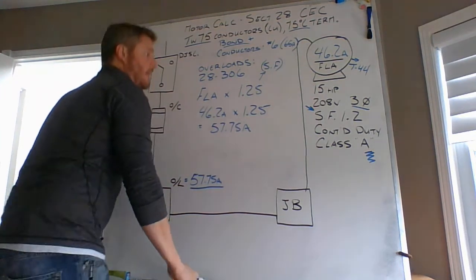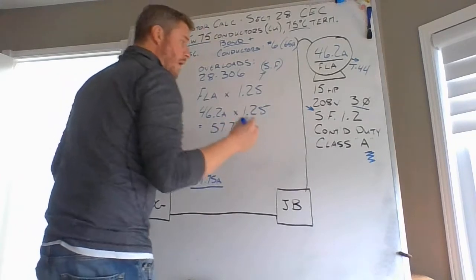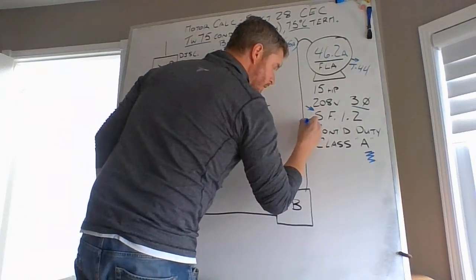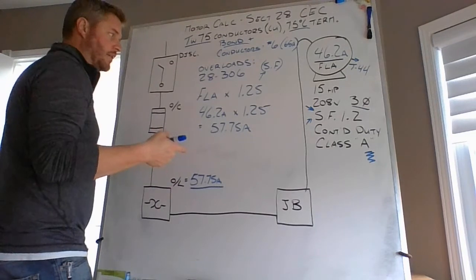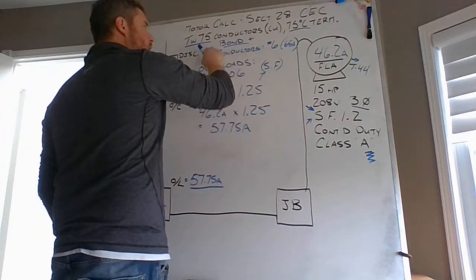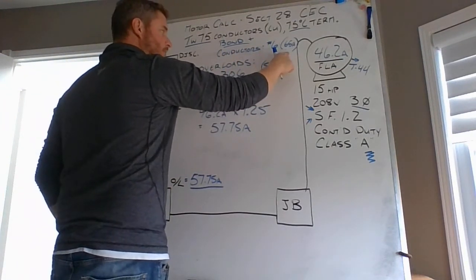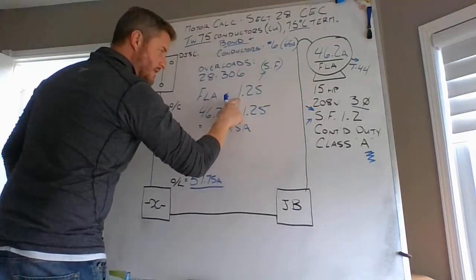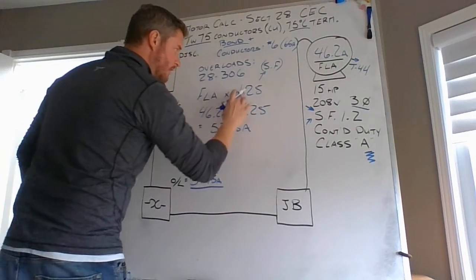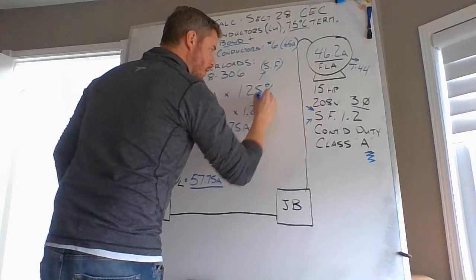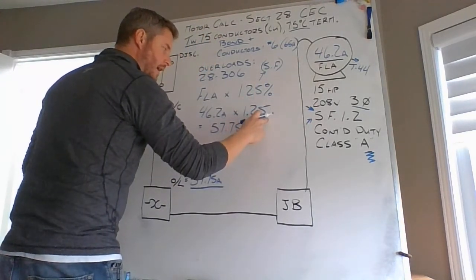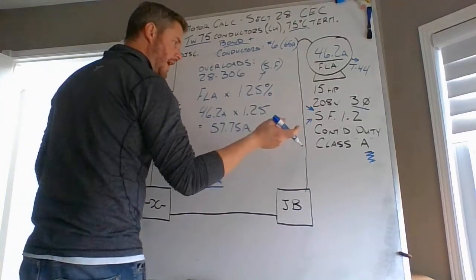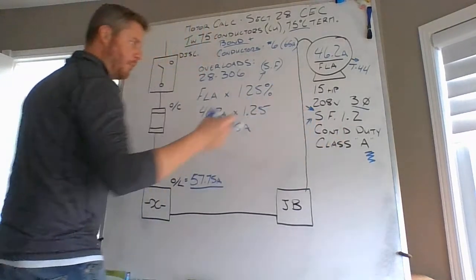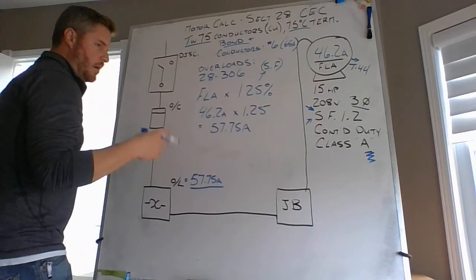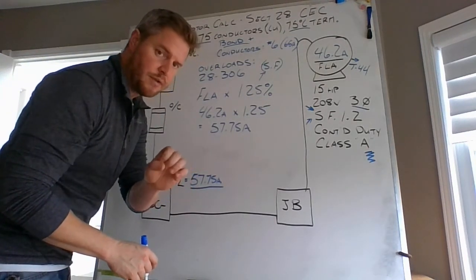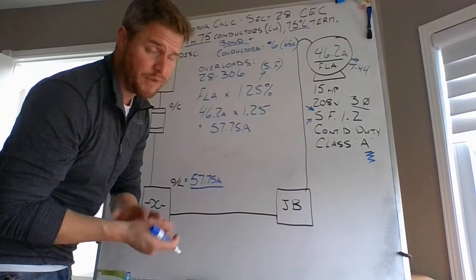It also comes down to being the same calculation. So when you move forward, you should be observing that service factor at the same time as doing your conductor calculation. It's the same multiplier, 125%, or a multiplier of 1.25. And you come up to the same number every single time based on the service factor being 1.2. So it is two different code rules. However, it's the same multiplier.